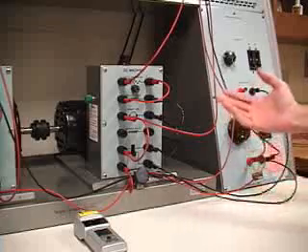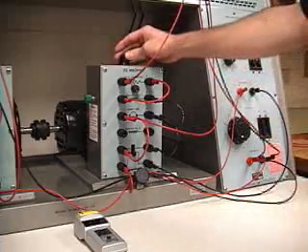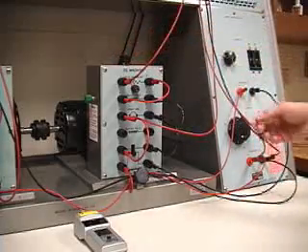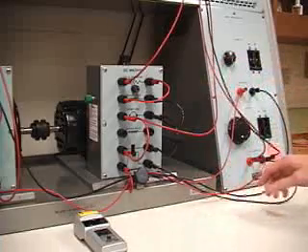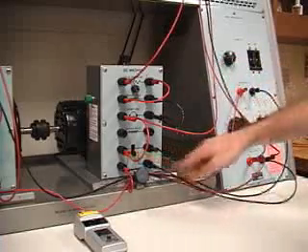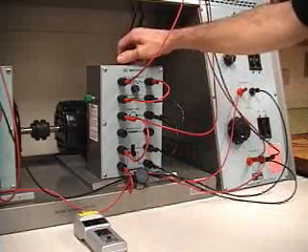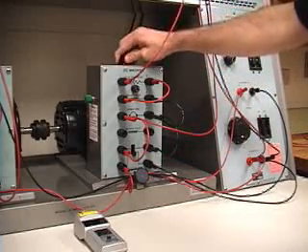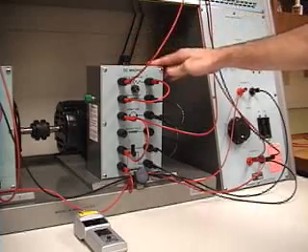First we're going to start up the DM100 DC machine which is configured as a self-excited DC motor. First step important in starting up the DC motor is have the circuit breaker initially off. Have the excitation field rheostat in its minimum position, not maximum, in a motor startup.